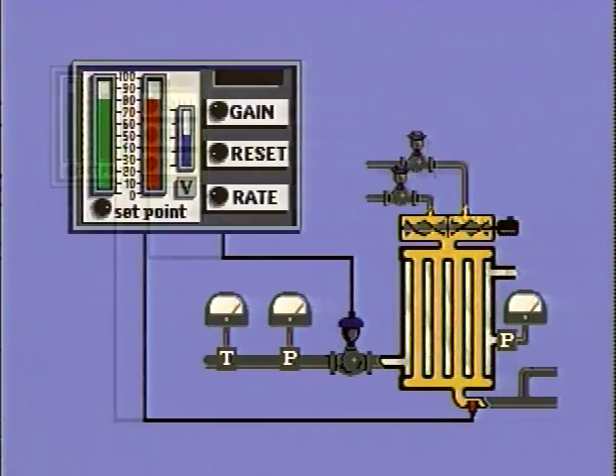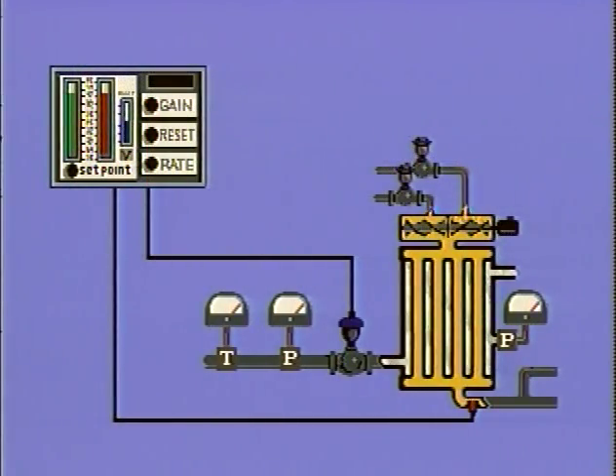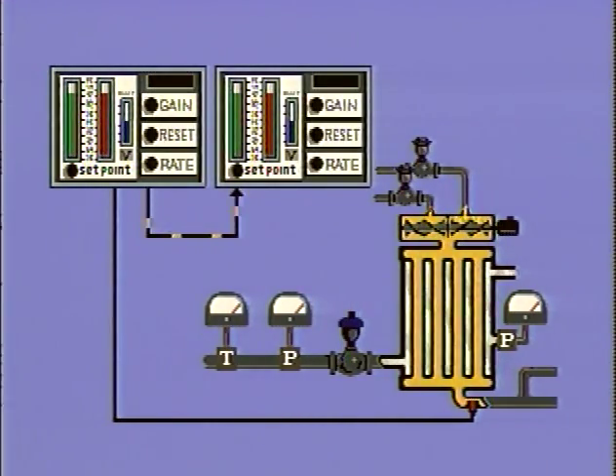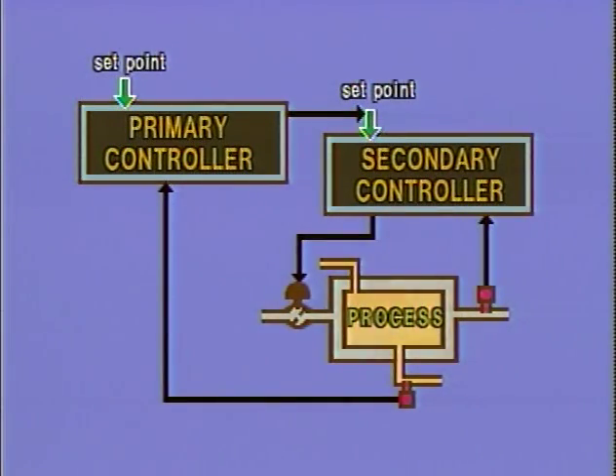The engineers felt that this was an ideal situation for cascade control. Cascade control involves using the output of one controller to provide an input to adjust the set point of a second controller. This second controller is part of a feedback loop inside the feedback loop for the primary variable. A simple block diagram illustrates this concept of installing one feedback loop within another.